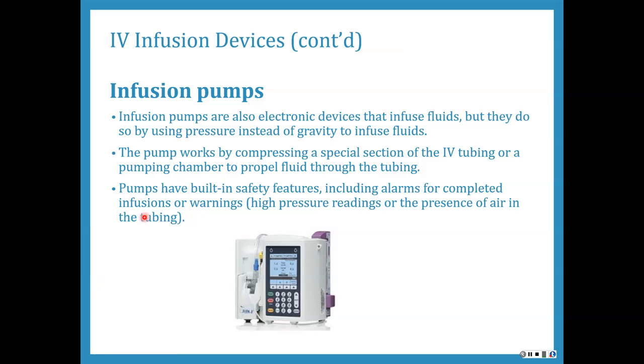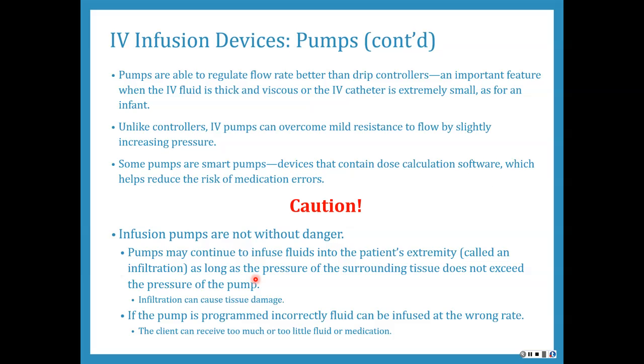If there is air, maybe you set the volume too high and you set it to deliver more fluid than what's in the bag, and then it'll instill all that fluid, but then when it starts to have air in the tube and air gets into this chamber, it will alarm and it will not allow you to instill air into the client. So it'll alarm and say that there's air present. So pretty cool technology that we have with the infusion pumps.